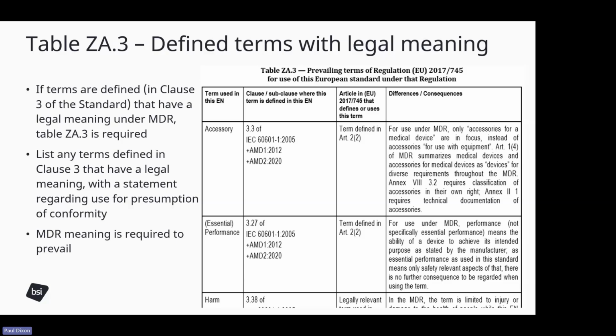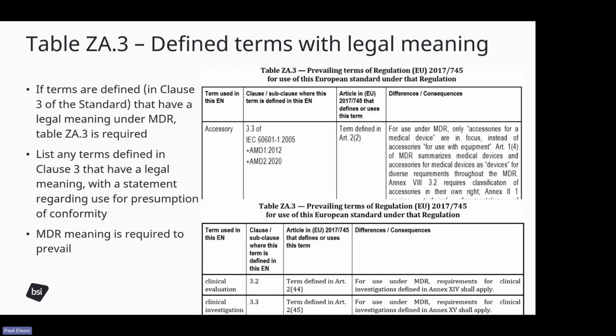So we create this table that lists the terms that are defined in clause 3 that also have a legal meaning, and a statement about how they are to be interpreted. So this is the term, this is where it has been defined in our standard, this is where it is defined in Article 2 of the MDR, and in this case, accessory. Use under MDR: only accessories for a medical device are focused, instead of accessories for use with equipment, and there are consequences of that. So the MDR meaning is required to prevail when the manufacturer is interpreting the standard. Another example, a different standard with clinical evaluation and clinical investigation, defined terms within the standard that have legal meaning.